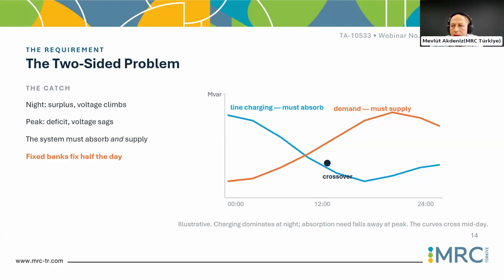And the very practical and first solution is putting some switched shunt reactors in these nodes. But then we face the voltage jump problem. So sizing the switched shunt reactors or making it dynamic variable compensation is a trade-off. Depending on the short circuit power at the grid connection point, we can either select shunt reactors or STATCOM or SVC. So we have different types of technologies giving not the same but similar results, serving a similar purpose, but the method and approach is different, cost is different, and technology is different.